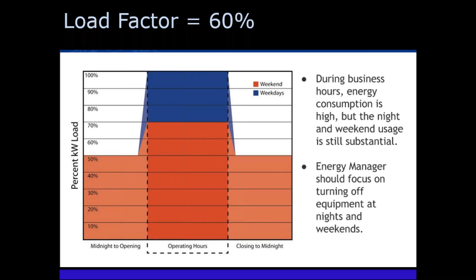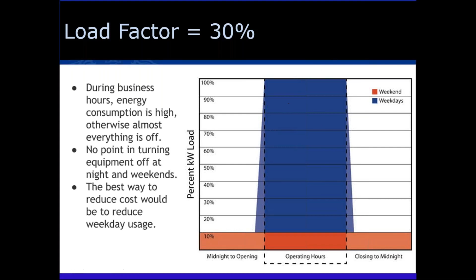Here's a load factor of 30. They use a lot during weekdays, then bring it down to about 10% at night, and on weekends nothing runs. That would be a school - schools are around 30%. The best way to reduce energy here is to target that weekday peak, since that's where the greatest opportunity seems to be.